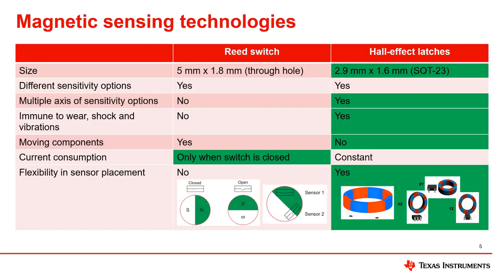There are two common types of magnetic sensors used in flow meters: reed switches and hall effect sensors. Reed switches consist of metal leads inside of a gas-filled tube that form a physical switch. When a magnetic field triggers the device, the metal leads touch and complete the circuit to indicate the magnetic field is present. Reed switches are popular because of their low power consumption and low cost, but are not immune to wear, shock, and vibration.